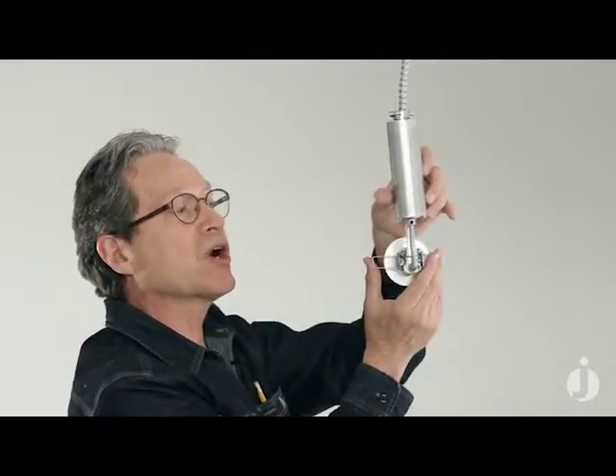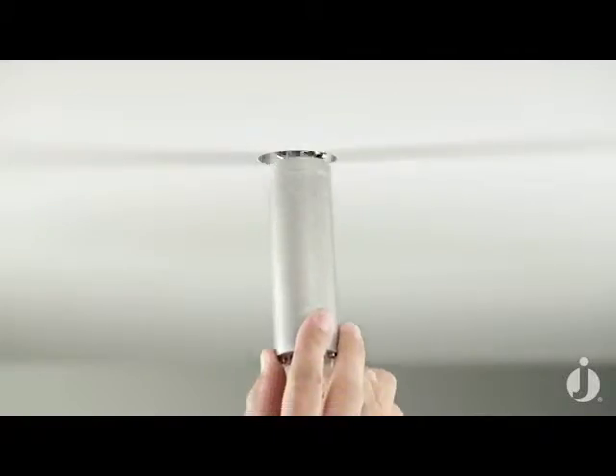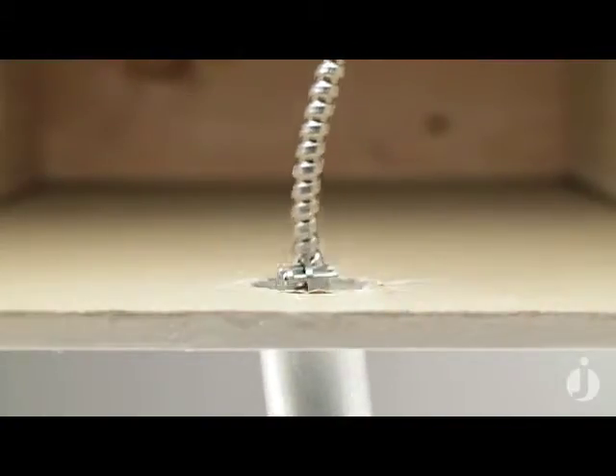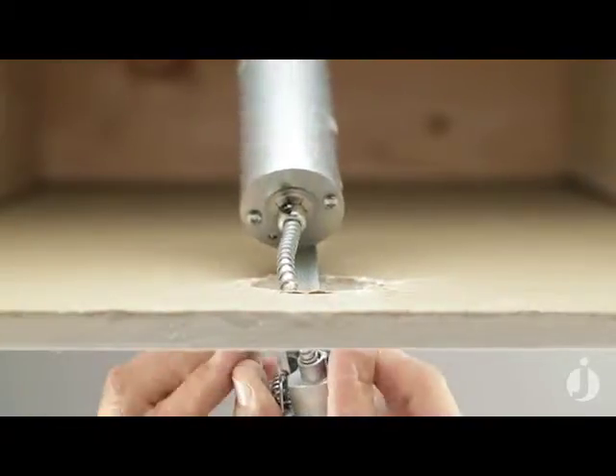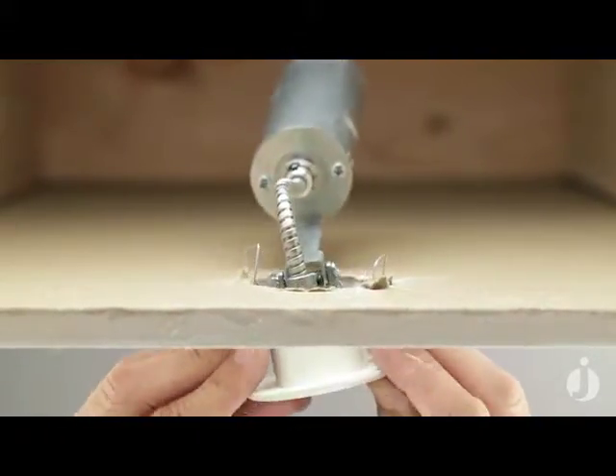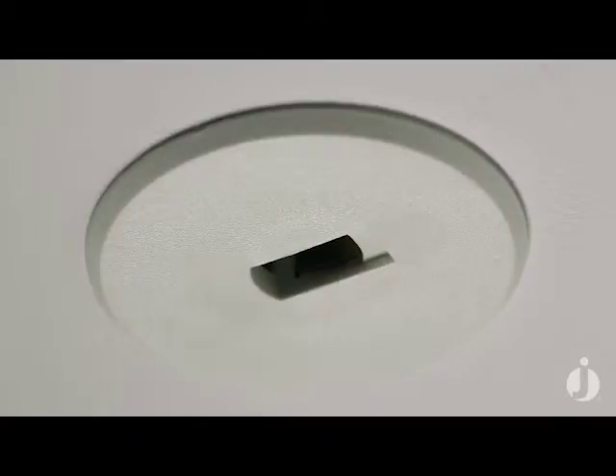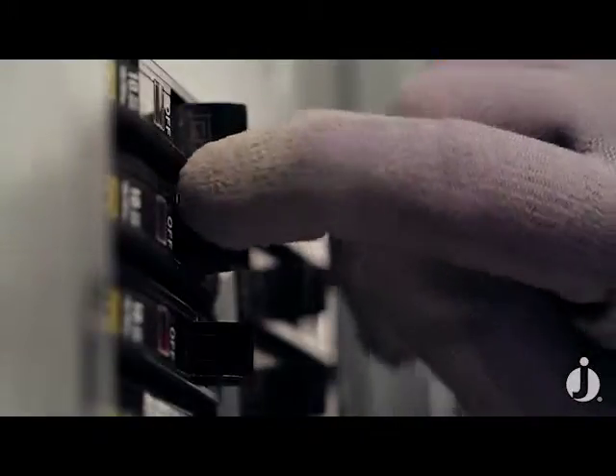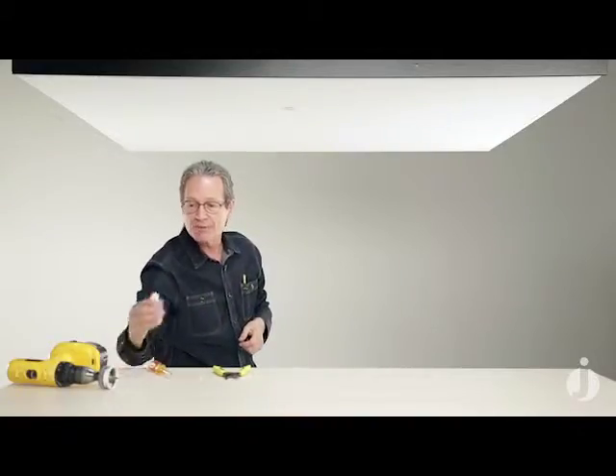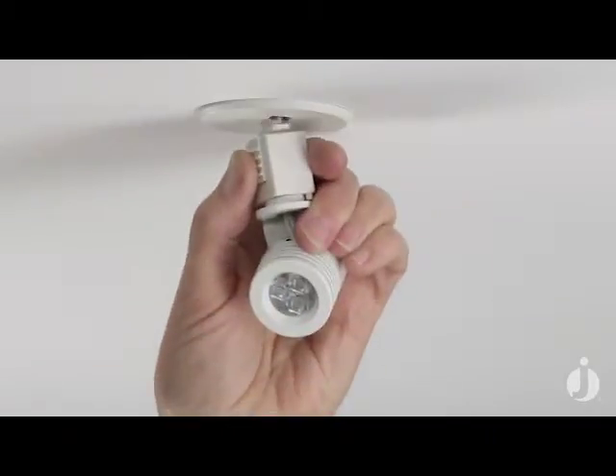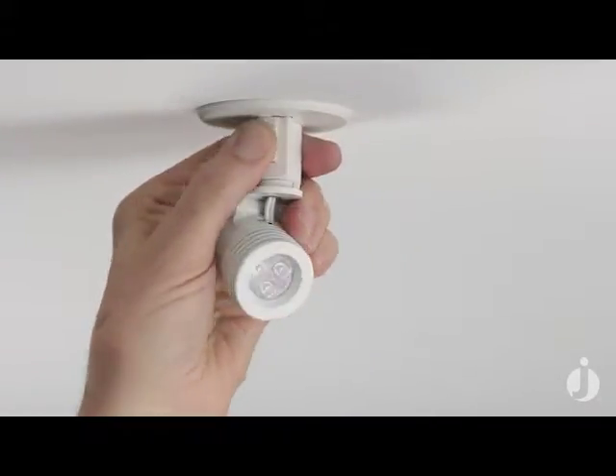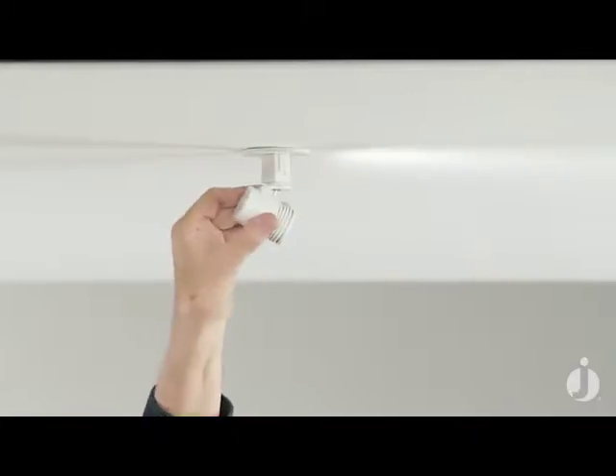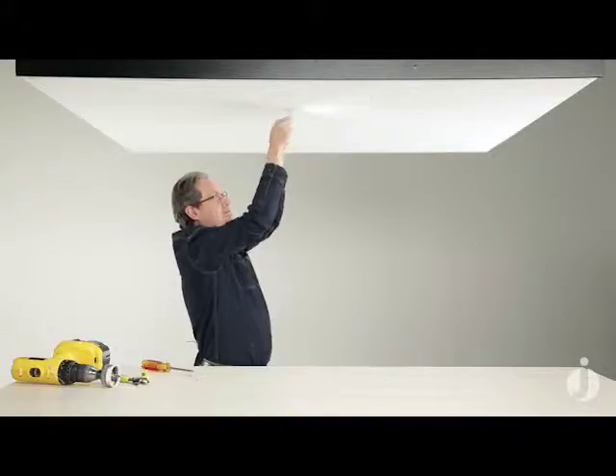Okay, now that the wiring compartment cover is on, I'm ready to actually install the product, and I'm going to push that transformer and wiring compartment through the ceiling and flex my springs vertically. There's my Mono-Point, nice and flush and tight to the ceiling. So the installation of our Mono-Point is complete. We'll restore power back at the circuit breaker box. And now let's try out a fixture. Again, I'm taking that little knurled part on the connector, and I'm going to twist that, and there you can see. Nice little directional fixture. And there you have it.